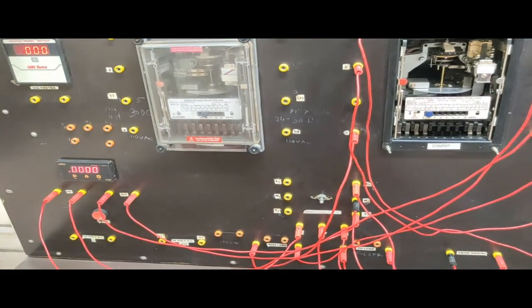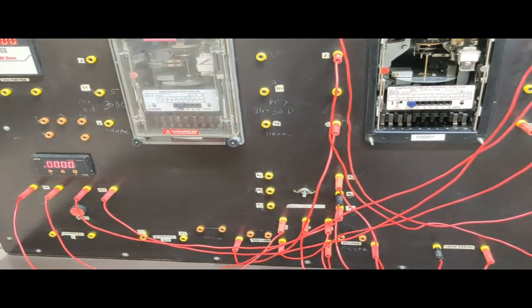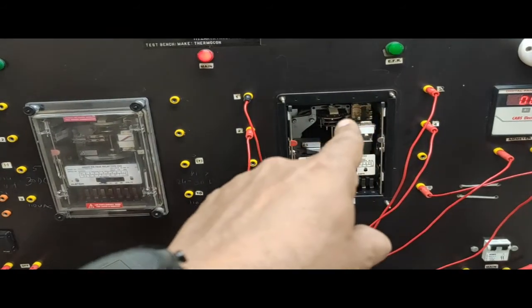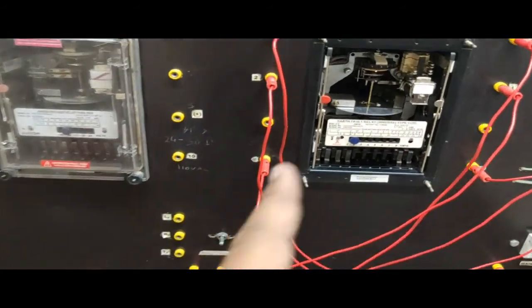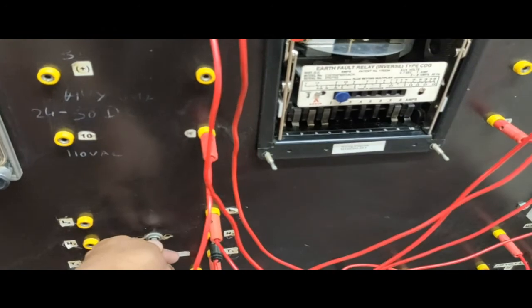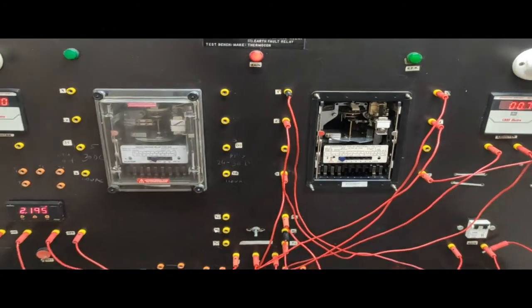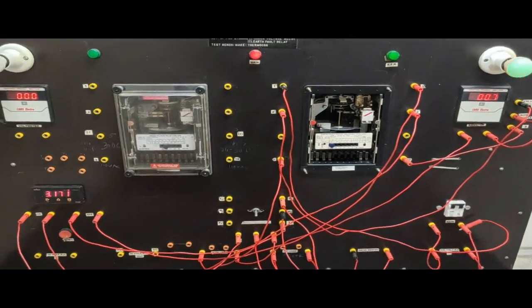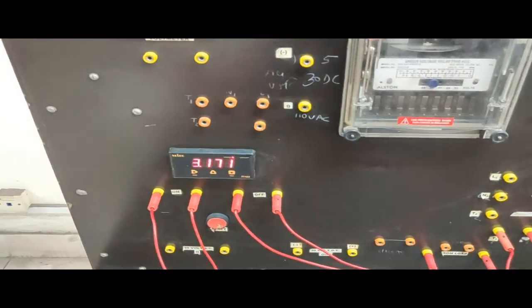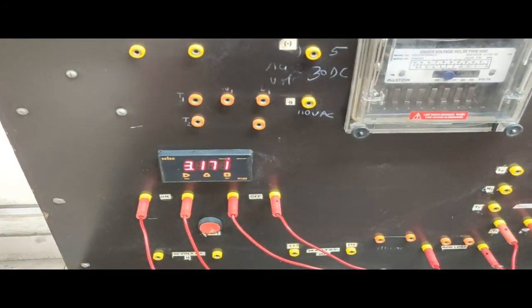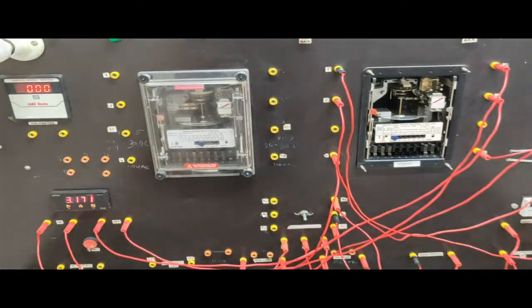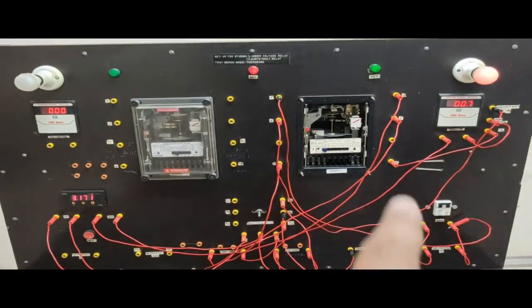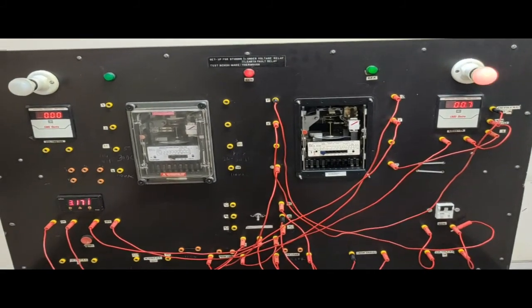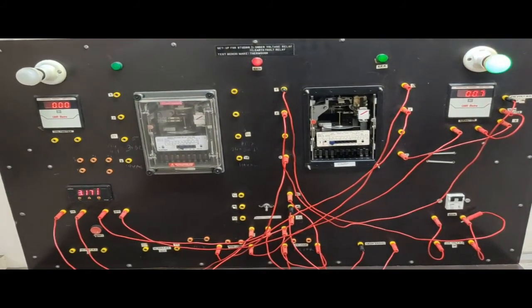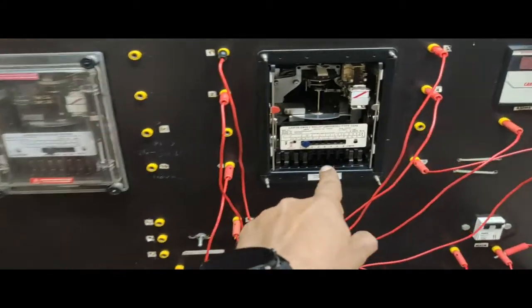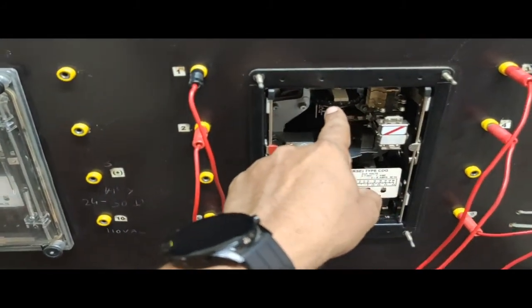Initially I think 5.7 seconds was required to operate the relay when the time setting multiplier was fixed at 1.0. Now it is set at 0.5. So just switch on the relay. The relay moves, generates the trip signal, and now you see that only 3.171 seconds is required to operate the relay. So that means the time of operation can be controlled using that dial, which is called the time setting multiplier, and the relay operating current can be controlled by the plug setting. So this is the plug setting and this is the time setting multiplier.